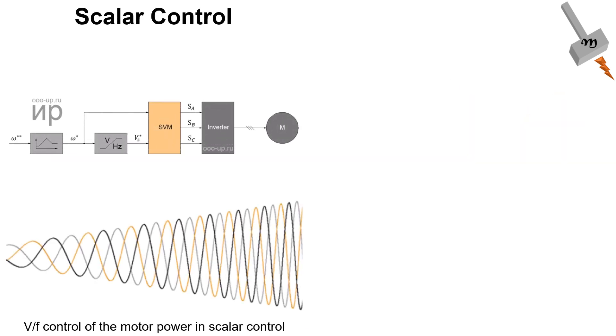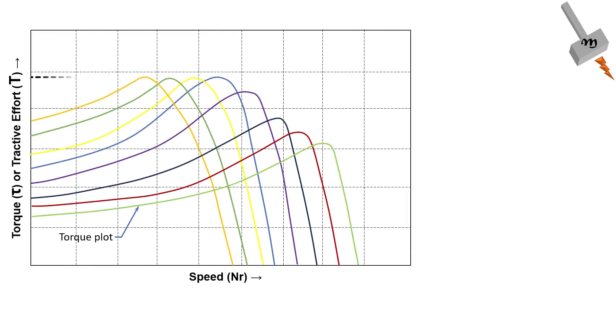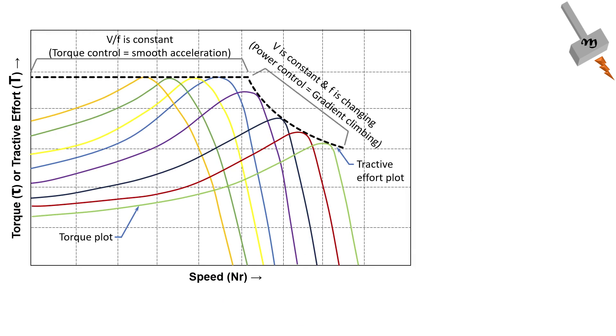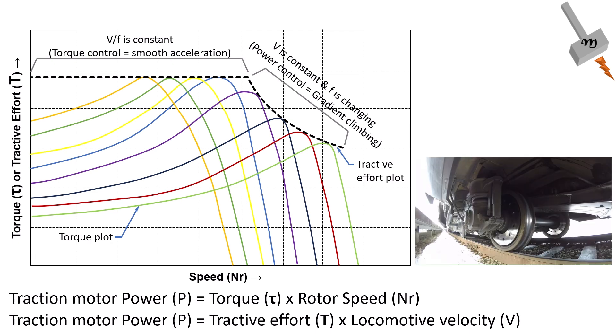Now let's get into the two types of speed control methods. Scalar control, also known as the V by F control, is the simpler of the two methods. It works by adjusting the ratio of the voltage to the frequency supplied to the motor to maintain a constant magnetic flux. The primary goal of scalar control is to ensure the strength of the motor's magnetic field remains constant, which results in consistent torque production.